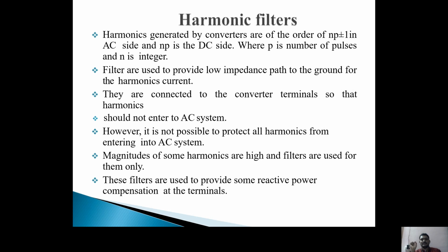Okay, they are connected to the converter terminal so that harmonics should not enter the AC system. However, it is not possible to prevent all harmonics from entering the AC system. The magnitudes of some harmonics are high and filters are used for them only. These filters, that is AC filters or DC filters, are used to provide some reactive power compensation at the terminals.